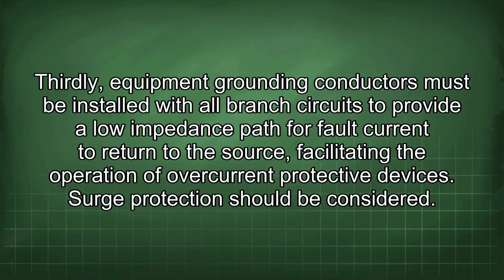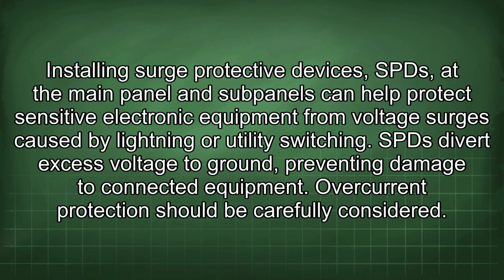Surge protection should be considered. Installing surge protective devices, SPDs, at the main panel and subpanels can help protect sensitive electronic equipment from voltage surges caused by lightning or utility switching. SPDs divert excess voltage to ground, preventing damage to connected equipment.